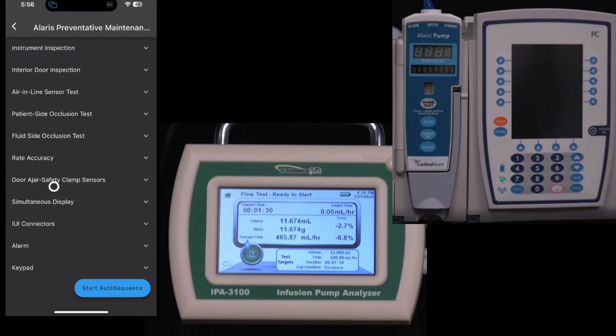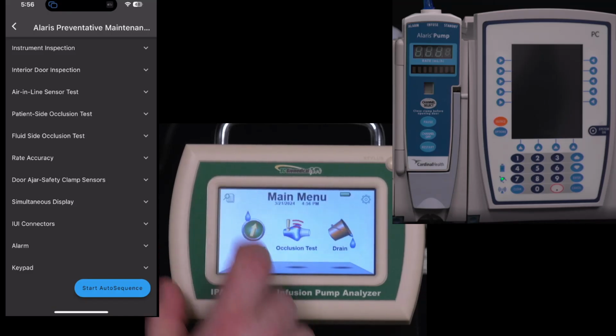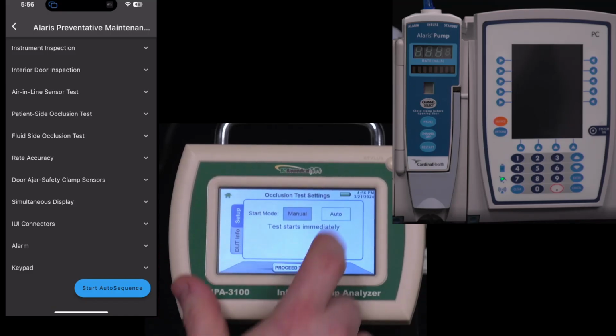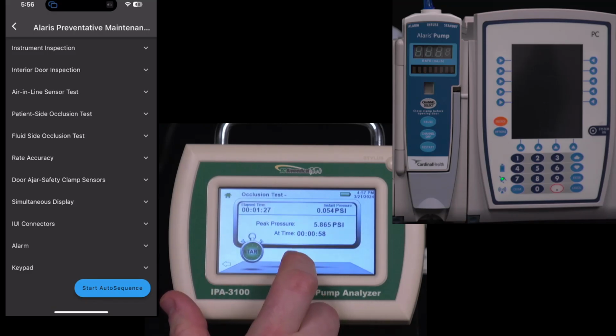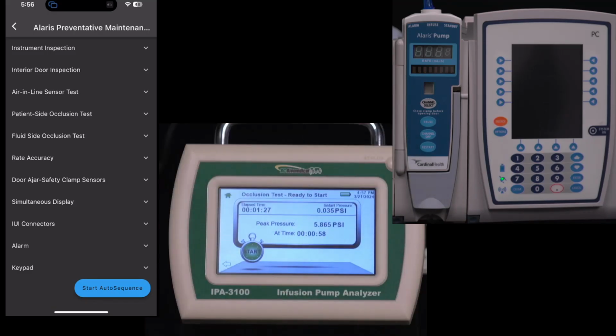Can this unit help us with pressure calibration? So pressure calibration, essentially, if you put this unit into occlusion mode, so we go to occlusion mode, we can... Pressure calibration, I'm assuming you would be using a hand pump or something to apply pressure to your infusion pump or other device? That's right. Yes. So hold on one second. I've got to take my headphones off. I'm going to go and get the hand pump. I've got one right here, actually.